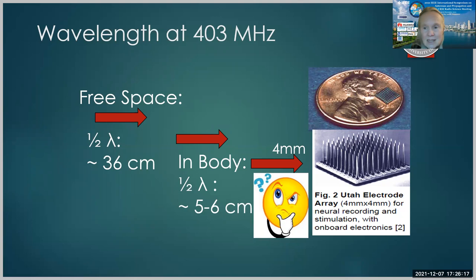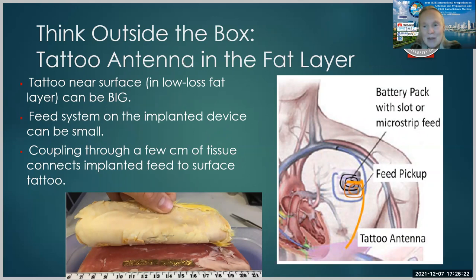So this actually requires thinking outside the box. In fact, thinking outside of the battery pack box. One example of this is something that we have proposed where you can do a tattoo antenna in the fat layer of the body. You could tattoo conductive nanoparticles near the surface in the low loss fat layer, and the tattoo can be quite large. The feed system on the implanted device could be very small, perhaps even four millimeters, and you could couple through a few centimeters of tissue to connect the implanted feed to the surface tattoo.